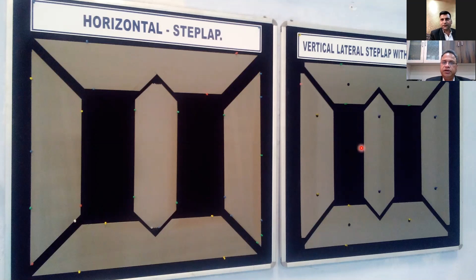Even people are using vertical step lap without this tip cut. But the advantage of cutting those tips is that it will make your transformer compact, and those sharp edges will be cut out. So during assembly it will be helpful, and as per safety norms it is more recommended. Also, flux will not dissipate from those corners; it will be directly aligned to the next step. So that is another advantage of the tip cut.